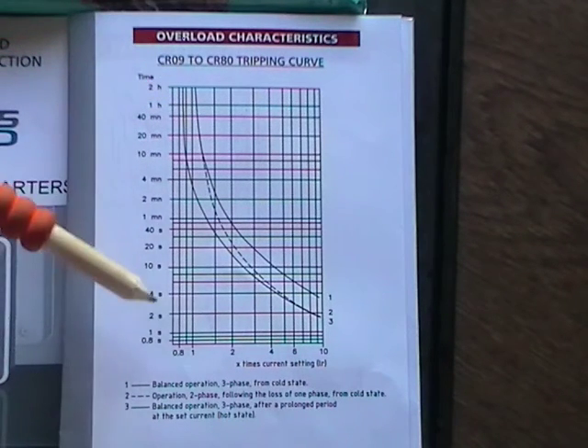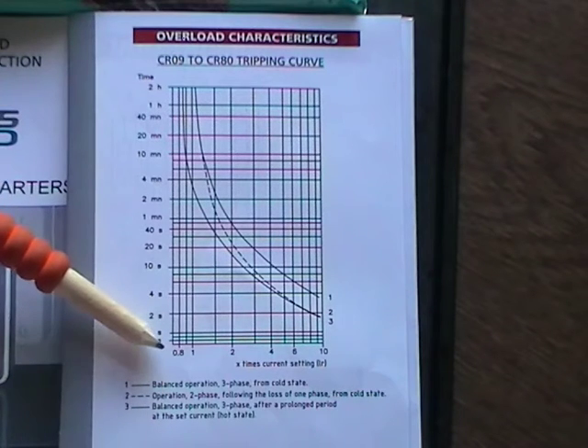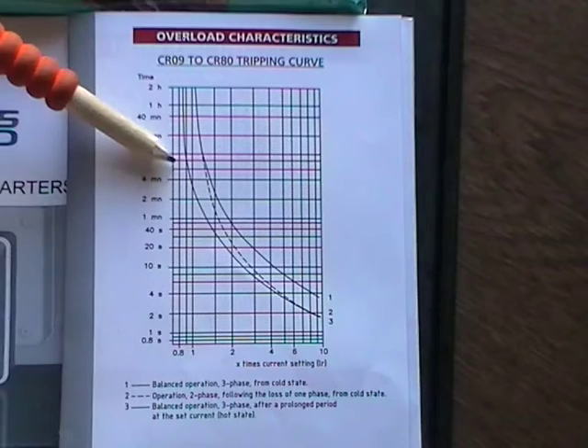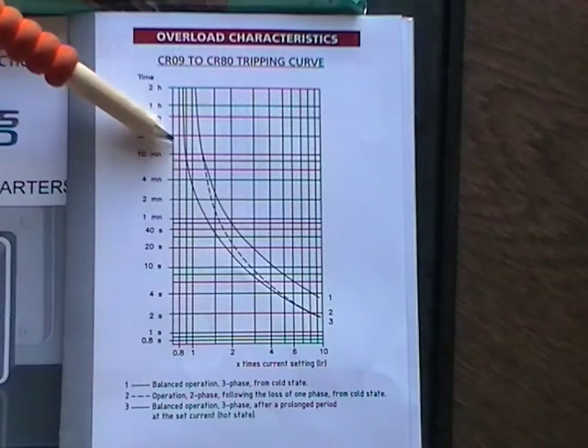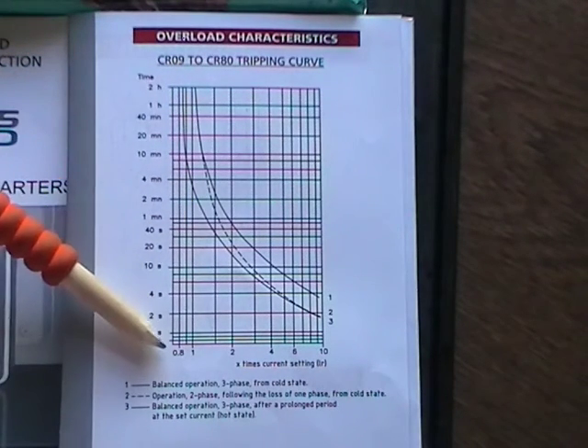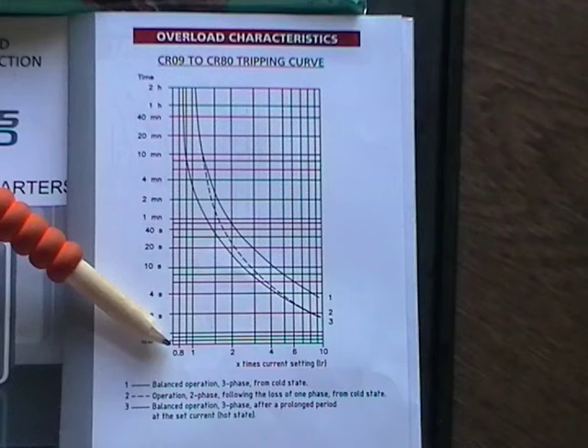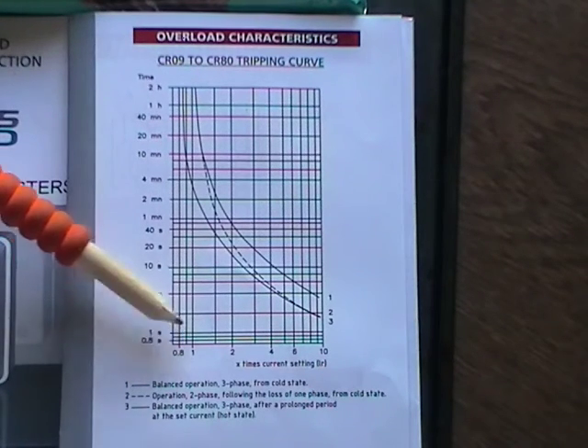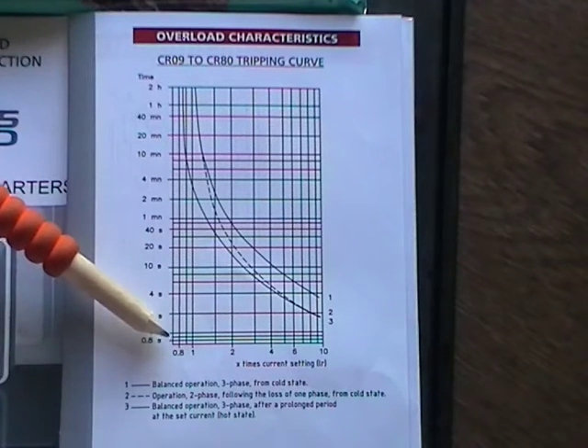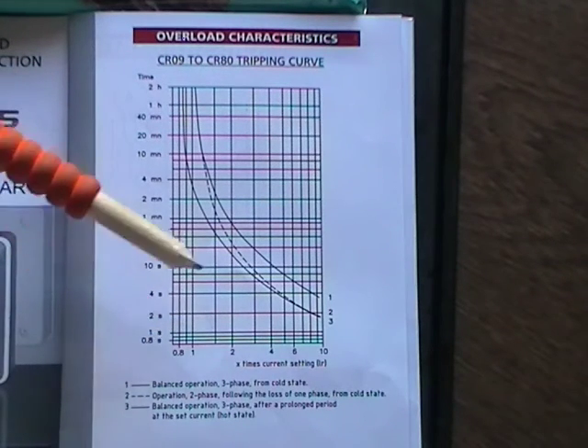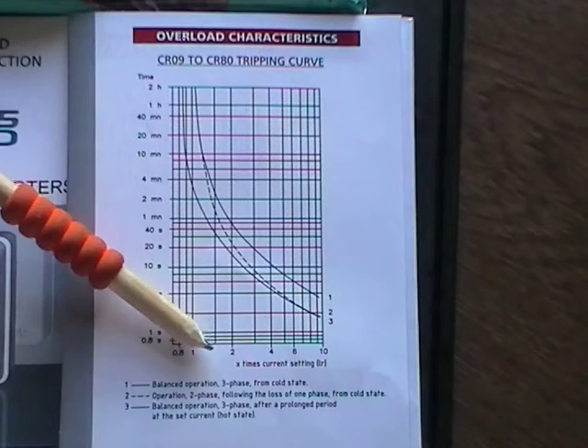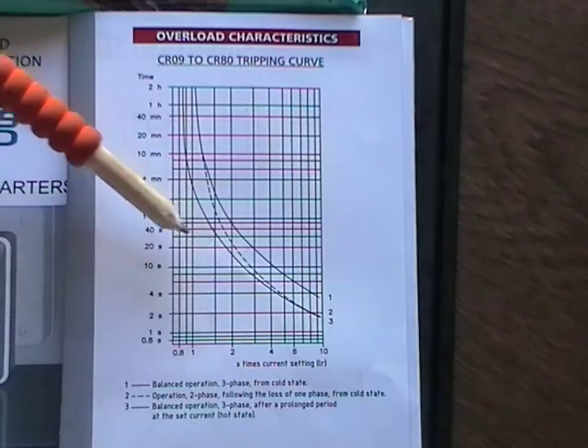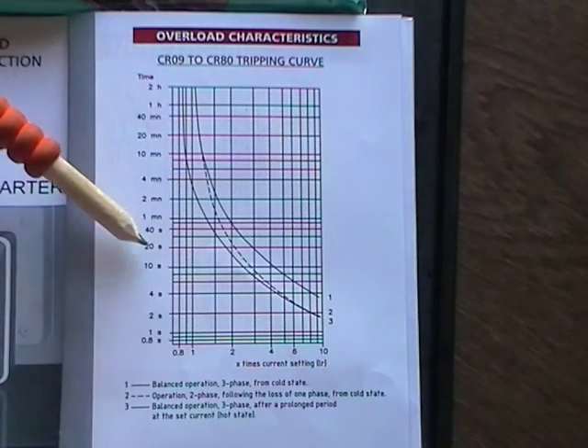If the motor is running at 0.8 full load, if we follow that line up, it never meets the hot curve, and therefore the motor will run indefinitely. As if we say that the 1 is 10 amps, that would be 8 amps. If the motor is further overloaded, say the current is doubled, then it reduces the length of time that the motor will run before the trips.